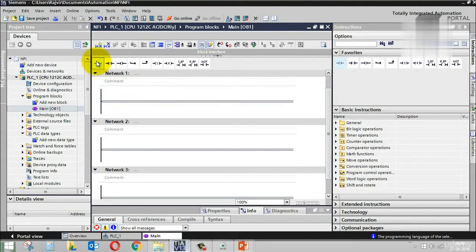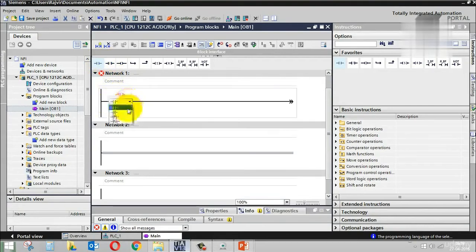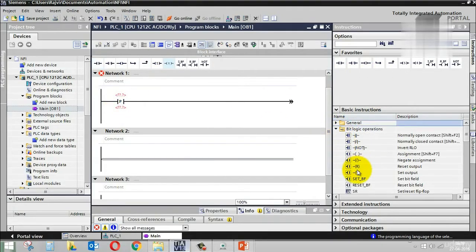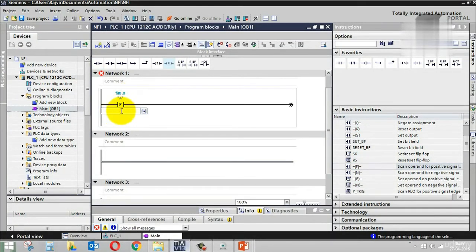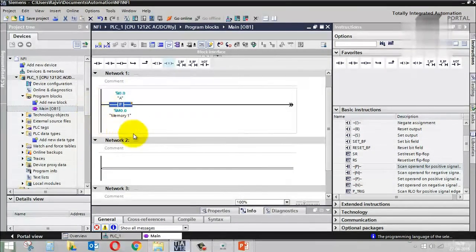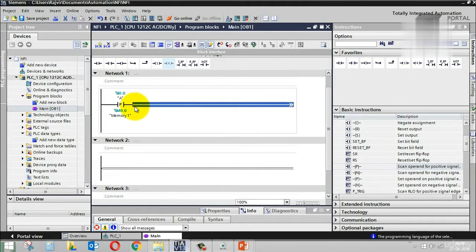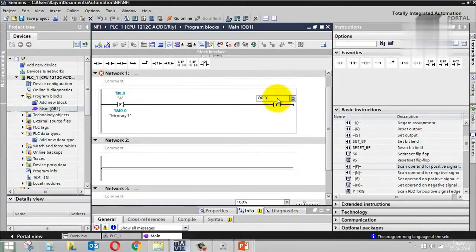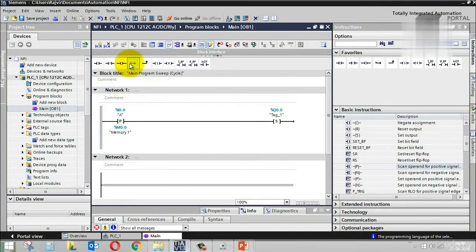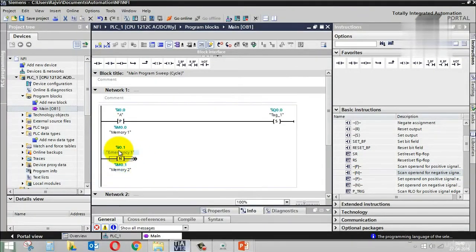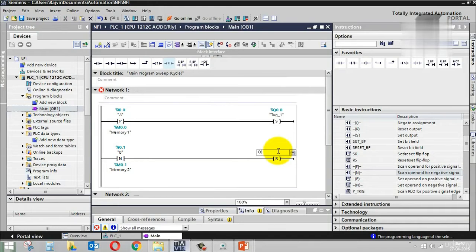Let's try this in Siemens TIA Portal. I'll take a positive edge contact with input I0.0 and memory bit M0.0. This is used to set output Q0.0. In parallel, I take a negative edge with input I0.1 and memory bit M0.1, used to reset output Q0.0. So I have a positive edge to set the output and a negative edge to reset it.